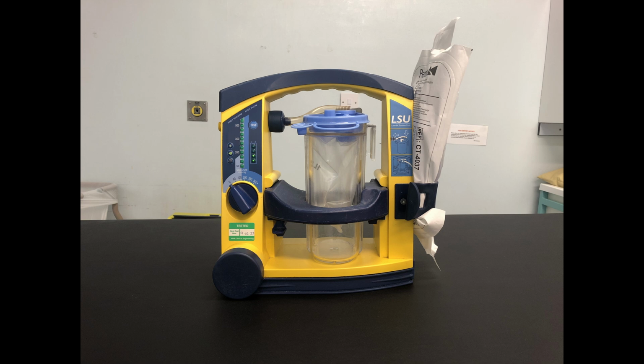The LSU is a portable electrically powered medical suction intended for field and transport use. It is for intermittent operation to remove secretions, blood or vomit from the patient's airway to allow ventilation. Higher vacuum levels are generally selected for oral and pharyngeal suctioning, darker blue, above 200 millimetres of mercury. Lower vacuum levels, in the pale blue section, below 200 millimetres of mercury, are usually selected for tracheal suctioning.